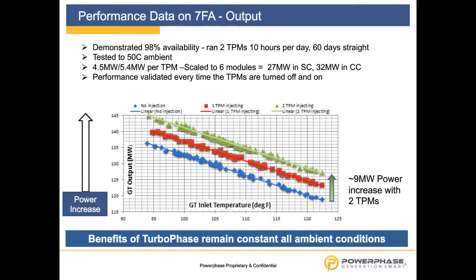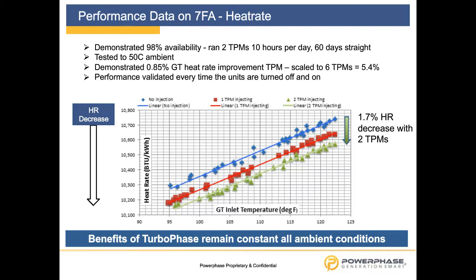I have the same graph, not for the output, but for the efficiency, the heat rate. The base heat rate is the blue line, which increases over the temperature. Then we have injected with the first TPM, similar to the other picture, the red line, and the second TPM is the green line. With the injection of 4.5 megawatt per TPM, we have decreased the heat rate by 0.85%. On this particular gas turbine, we could have installed 6 TPMs, decreasing the heat rate, accounting for direct fuel savings, to 5.4%.